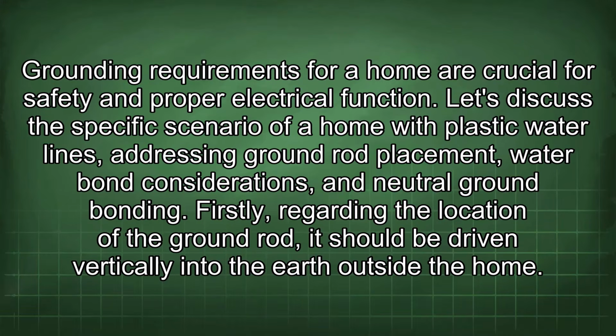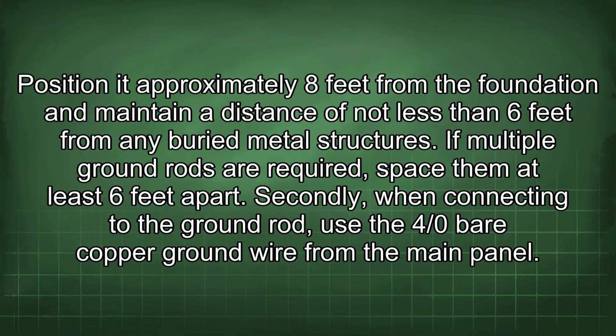Grounding requirements for a home are crucial for safety and proper electrical function. Let's discuss the specific scenario of a home with plastic water lines, addressing ground rod placement, water bond considerations, and neutral ground bonding. Firstly, regarding the location of the ground rod, it should be driven vertically into the earth outside the home.